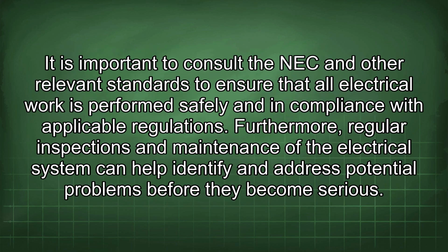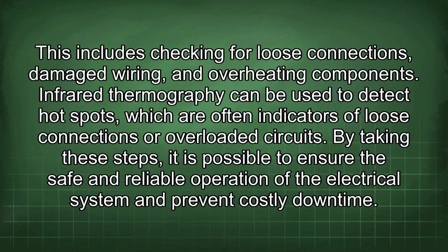It is important to consult the NEC and other relevant standards to ensure that all electrical work is performed safely and in compliance with applicable regulations. Furthermore, regular inspections and maintenance of the electrical system can help identify and address potential problems before they become serious. This includes checking for loose connections, damaged wiring, and overheating components. Infrared thermography can be used to detect hot spots, which are often indicators of loose connections or overloaded circuits.